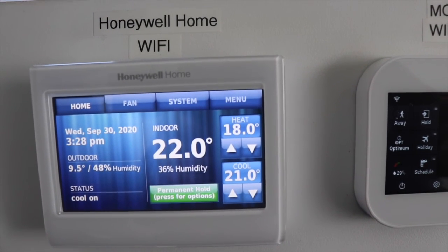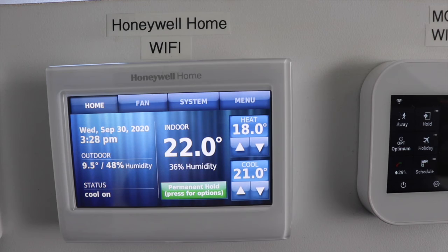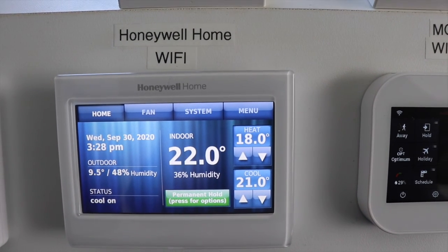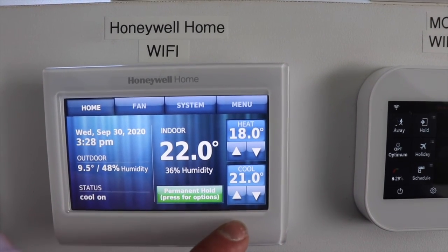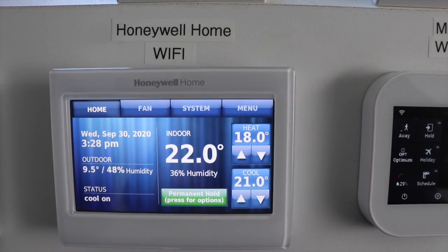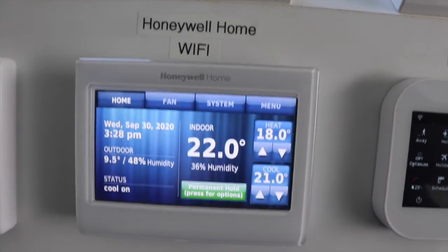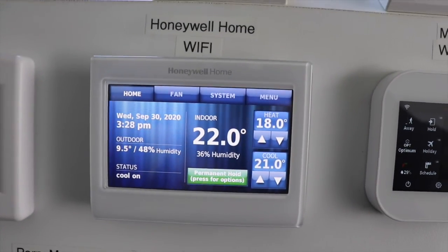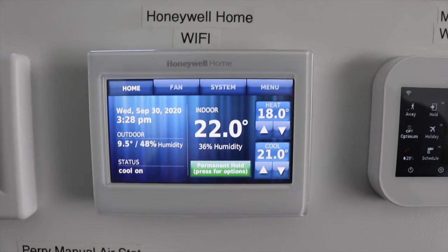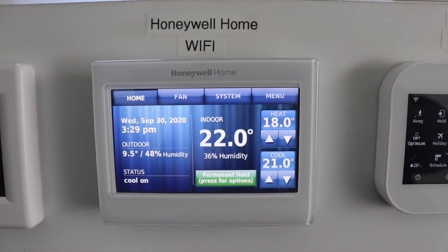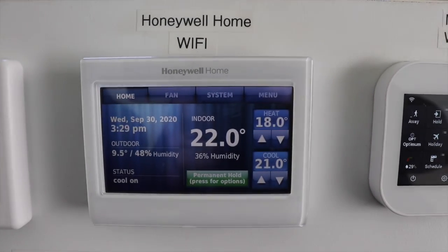If it's in heating mode, the slab stat and the air stat will work together, but the second that this thermostat says it's too hot and it wants to cool down, it will lock out the slab stat and start cooling down the house and turn on your blowers or cassette. Or ducted system? Yes. Okay, thanks Craig, we'll have a go.